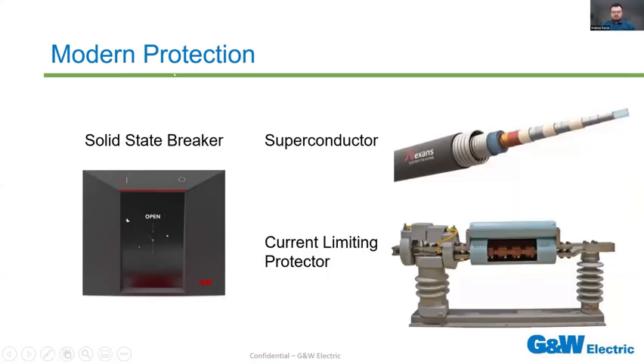So here are some different images and examples of all these different modern current limiting devices. On the left, you have the ABB solid-state breaker. You can see that it almost looks like a monolith. There are no visible mechanical parts and very few buttons to interact with on the front. Basically, there's an indicator to let you know whether it's open or closed, a power button, and some extra buttons for status updates.